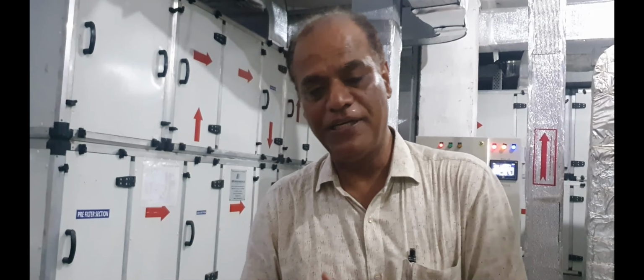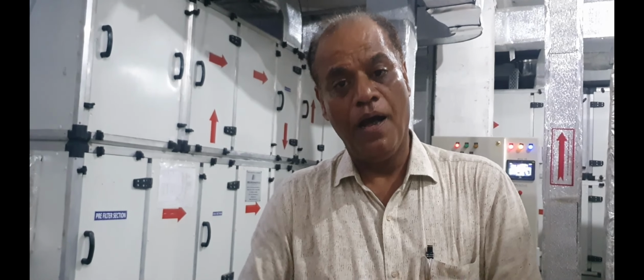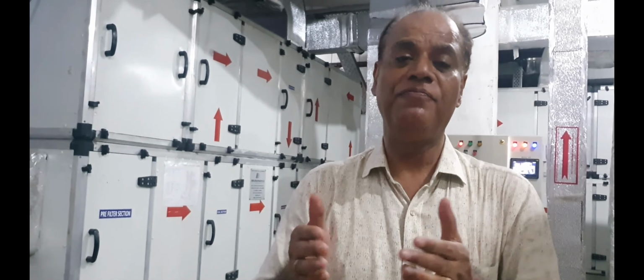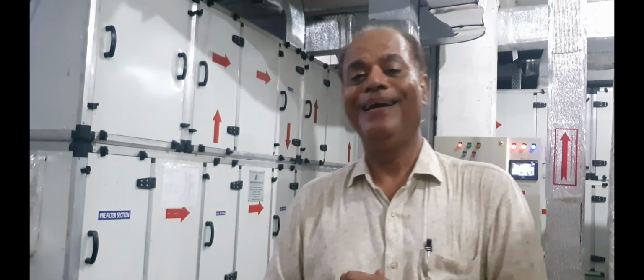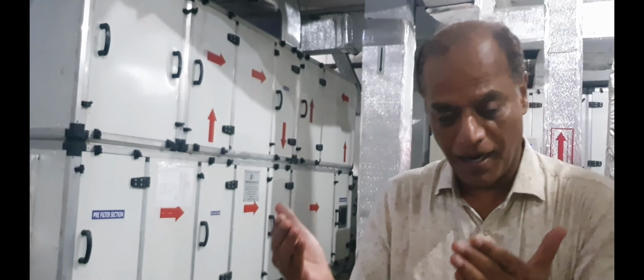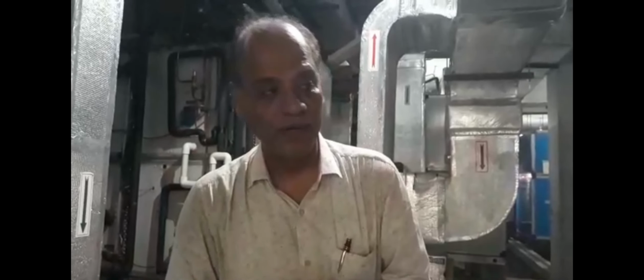Here every machine has individual condensing units, and from one of the machines we have generated hot water. This hot water is used for controlling the RH by reheating the air. All these 4 AHU cum humidifiers working on the EM series principle save 40% power, which amounts to 49 kW in absolute terms. If a conventional humidifier was used, the client would have been consuming 49 kW additional power, almost 40% less power of the total.